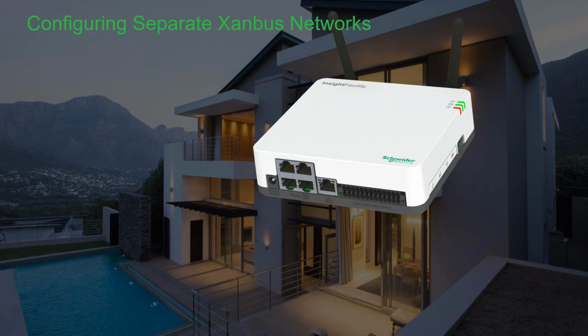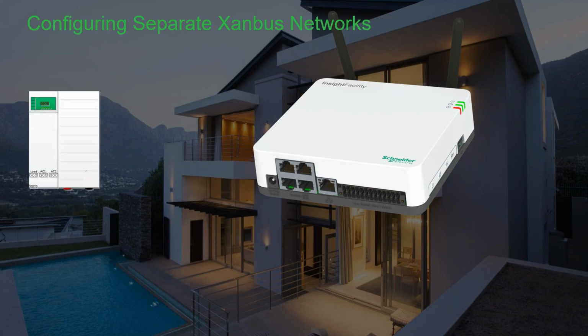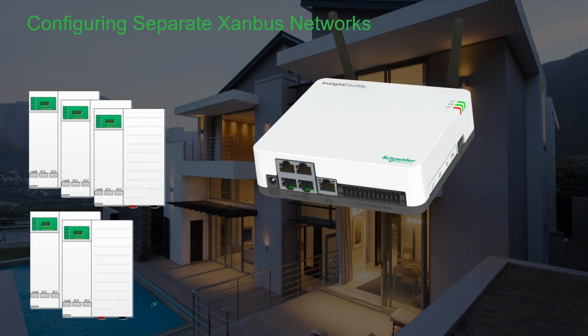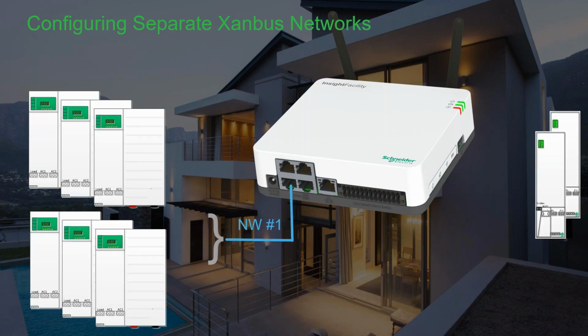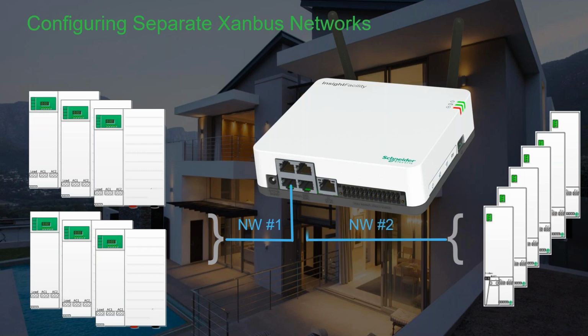Xanbus is an isolated network. As such, there is no grounding in the RJ45 jack for shielded cable. This is why we provide grounded raceways in our balance of system components. Xanbus cables must not be routed in parallel with AC current carrying conductors. A single Xanbus network can accommodate 6 XW Pro units plus the battery monitor, AGS, and SCP when configured for 3-phase.